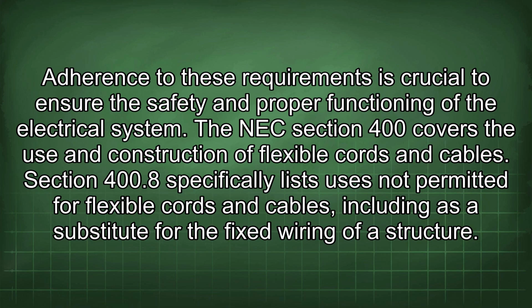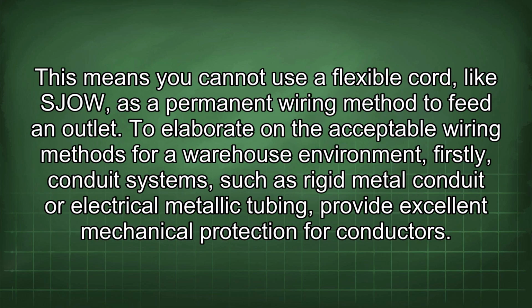The NEC Section 400 covers the use and construction of flexible cords and cables. Section 400.8 specifically lists uses not permitted for flexible cords and cables, including as a substitute for the fixed wiring of a structure.